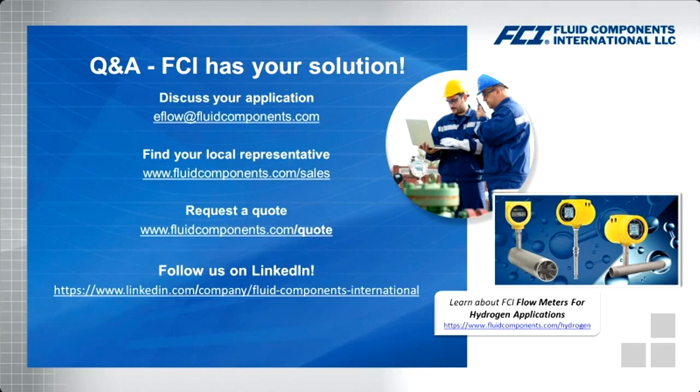It makes thermal dispersion much more effective in those applications because we don't care about that low density. One thing I will say, though, when using a thermal meter, you need to be sure that it is calibrated in hydrogen gas for the application.